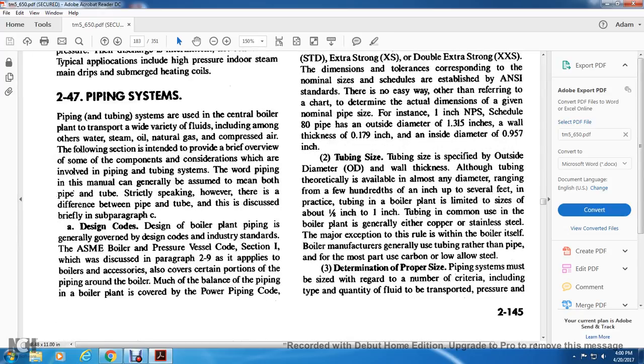Piping and tubing systems. Piping and tubing systems are used with the central boiler plant to transport a wide variety of fluids, including water, steam, oil, natural gas, and compressed air. The following section is intended to be a brief overview of some of the components considered in piping and tubing systems. The word piping is generally assumed to mean piping and tubing. Strictly speaking, however, there is a difference between piping and tubing, which is discussed briefly in subparagraph C.